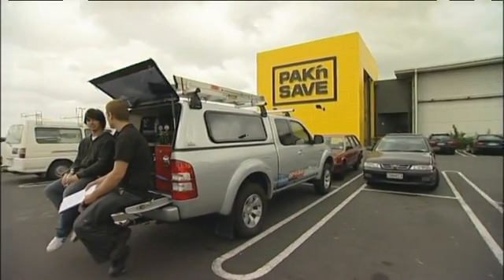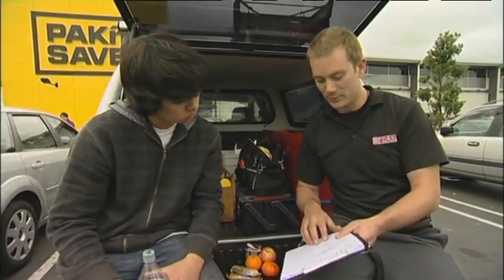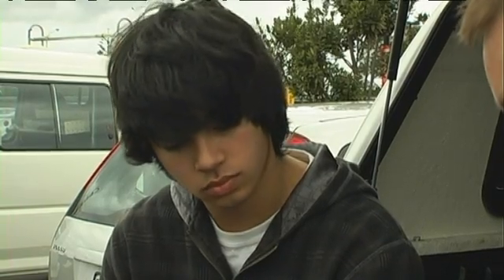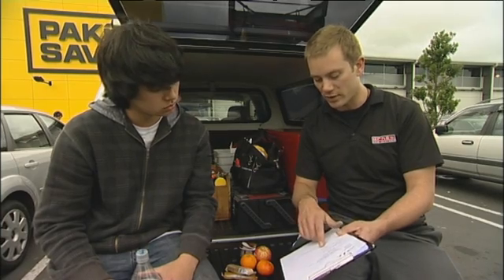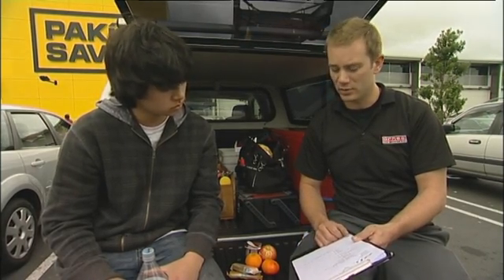James is just being faxed the results of the oil test done the previous day. What we've got here are the oil results from yesterday. You can see throughout the test they've taken that the water parts per million came back slightly high, so we recommend doing a dry change on that to remove the moisture.